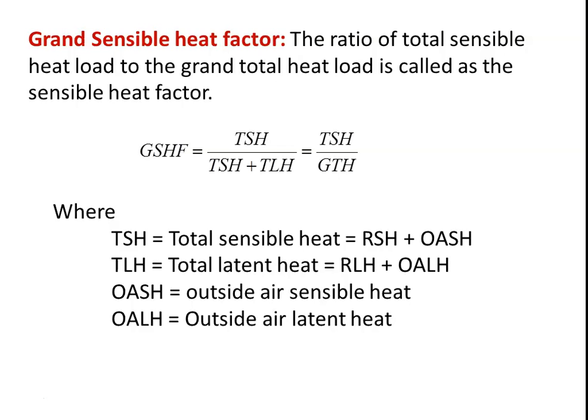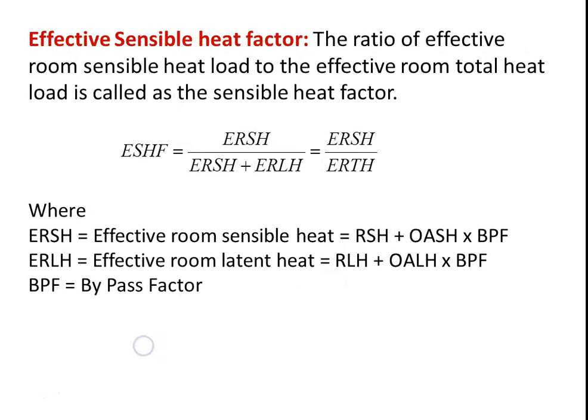So what is sensible heat? Adjusting the temperature is the sensible heat. Adjusting the moisture is the latent heat. So when you add water vapor or remove water vapor, that changes the latent heat. When you heat the air or cool the air, that changes the sensible heat. And the effective sensible heat factor is the ratio of effective room sensible heat divided by effective room sensible heat plus effective room latent heat. So this is effective room sensible heat divided by effective room total heat.